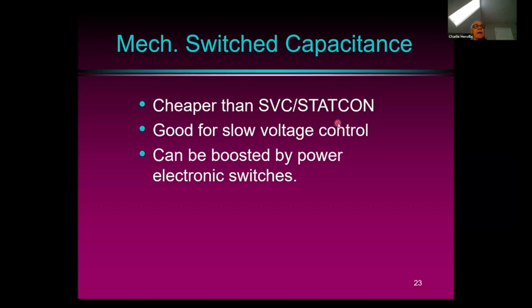They do take a little bit of time to switch on, but you may have power electronic switches. One person I know was advocating the use of shunt capacitors with a power electronic switch across one layer. So if the voltage goes down, you just short out one layer of the shunt capacitance, and all of a sudden you get more reactive power out of the remaining capacitors.